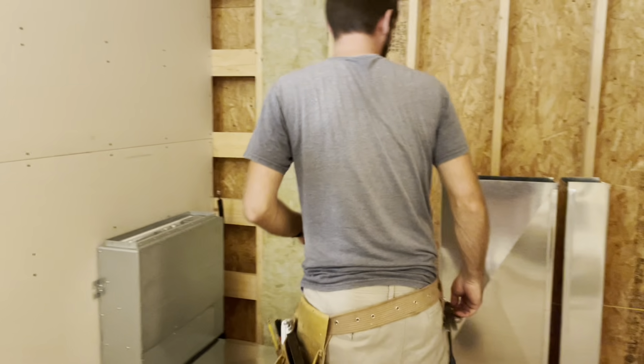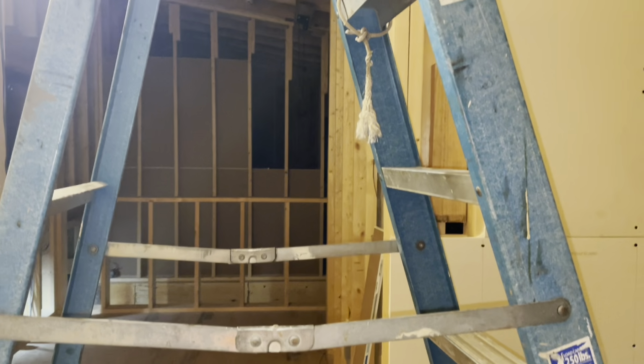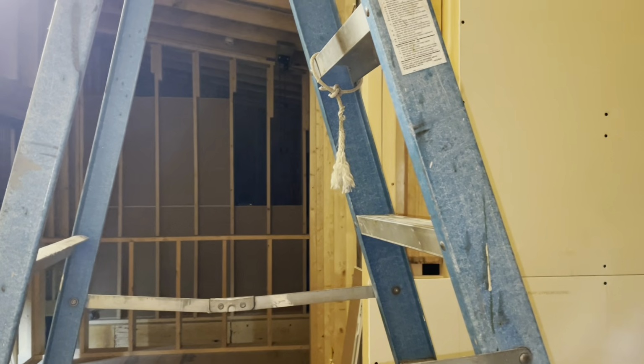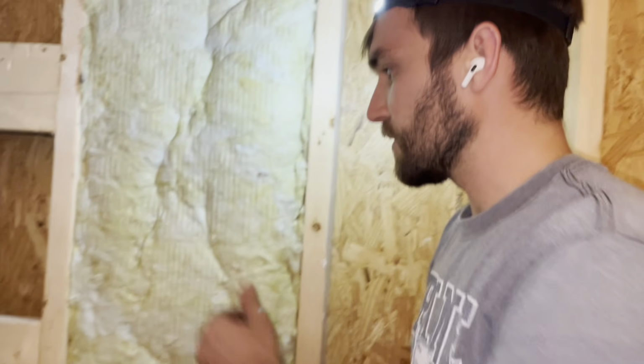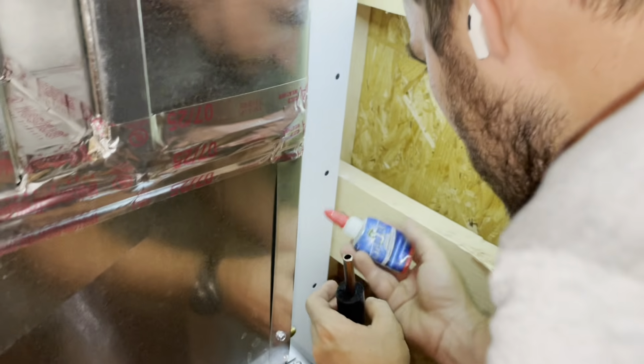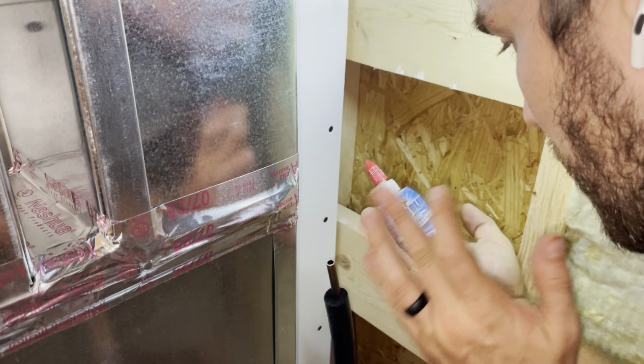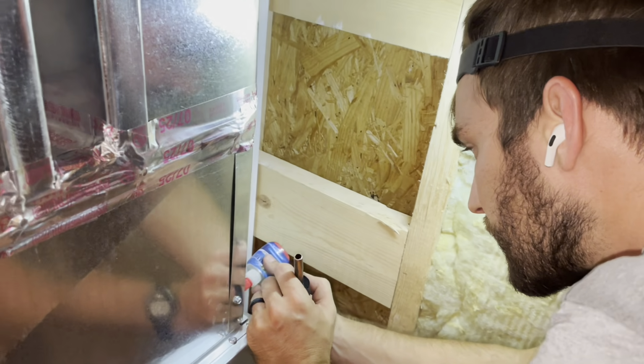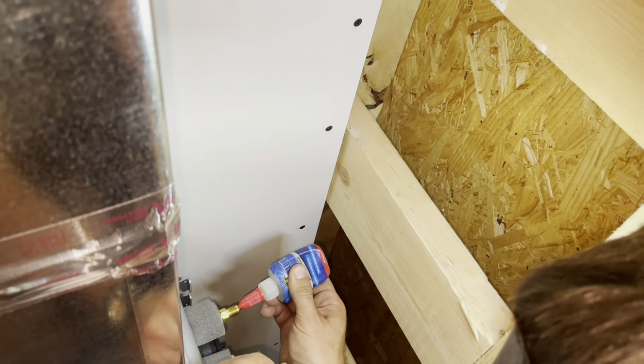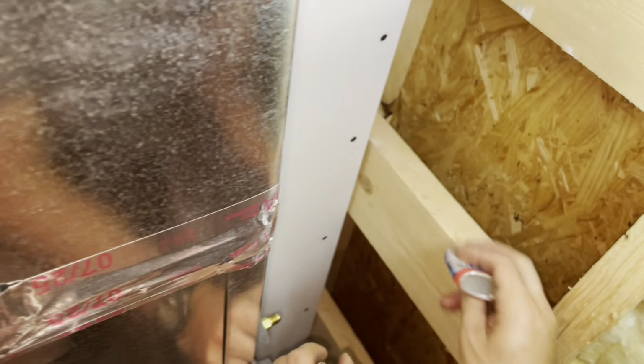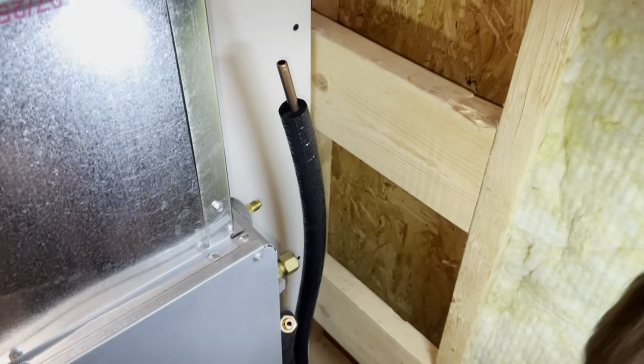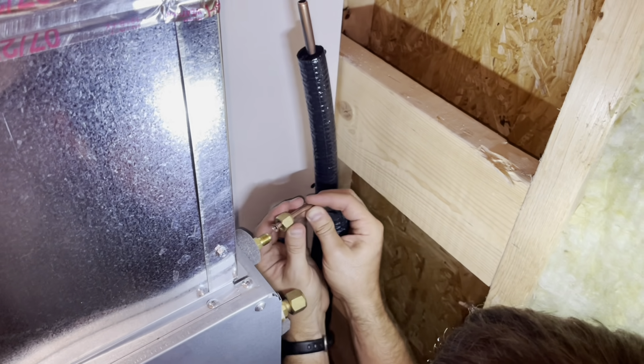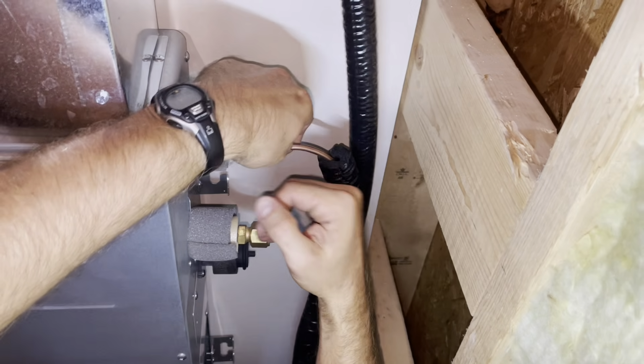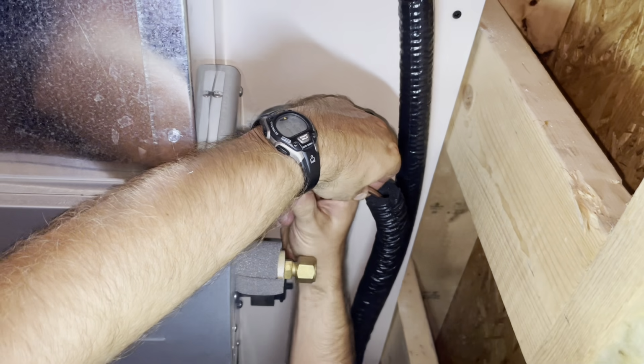Aaron's moving the upstairs units into place. They're a little bit weird because this unit serves both this bedroom and the bathroom over there, and then the unit in that room serves this front office area and that bedroom. I'll throw some Nylog blue on there. What's that do? It is a gasket and thread sealant compatible with all refrigerants. So I just put that right on the seat. Probably not really necessary, but you know, people swear by it, so whatever. Very nice. I'd be so stressed about this cross-threading. Can't really cross thread them.